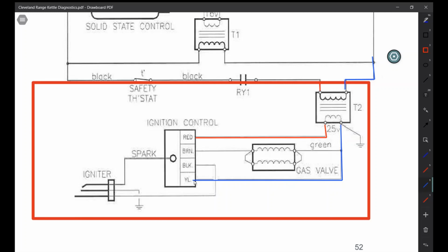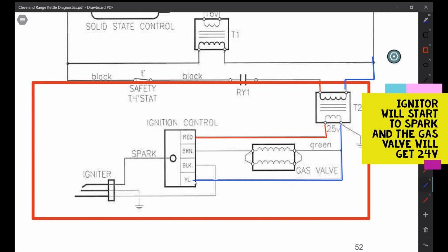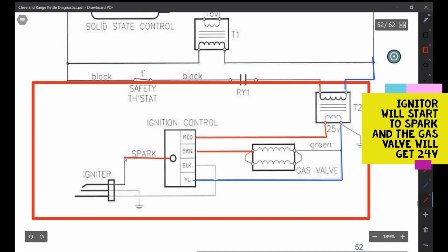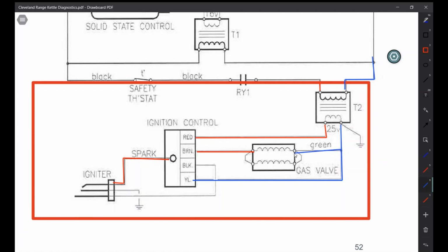As soon as we get 24 volts to the module, the igniter will then start sparking, 24 volts to the gas valve immediately. We then get a 1 microamp signal from the flame sensor sent back on this black wire right here. And then the sparker will turn off.